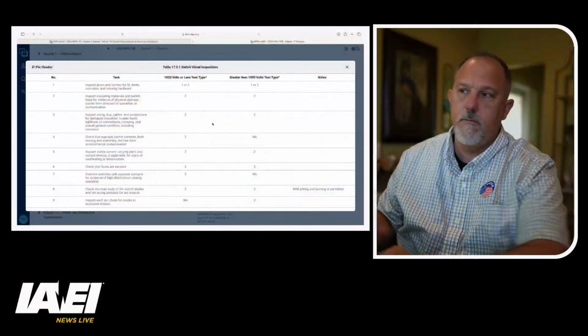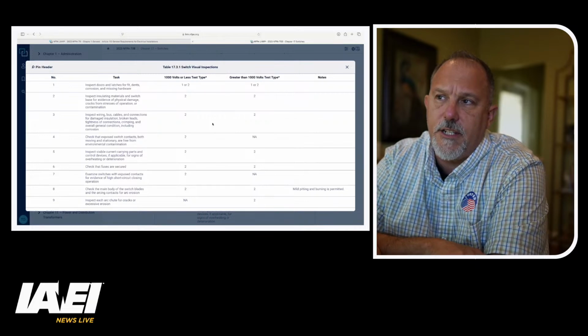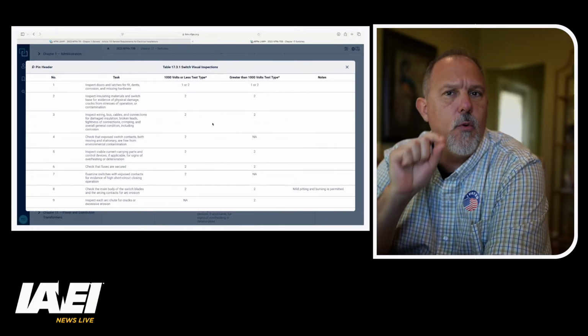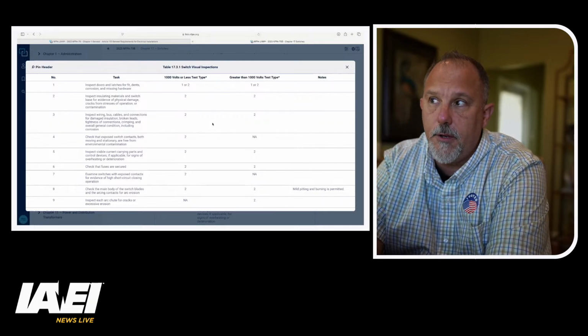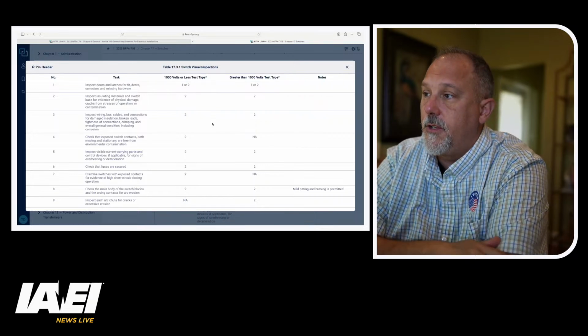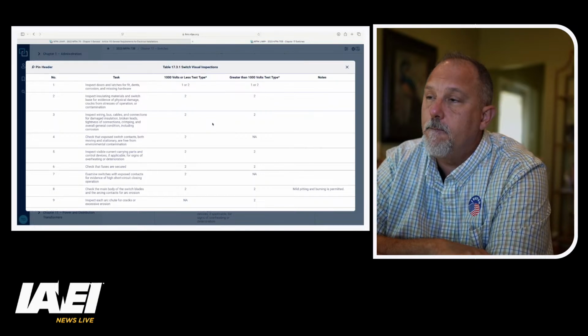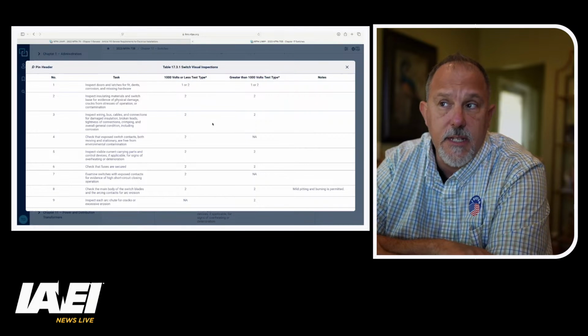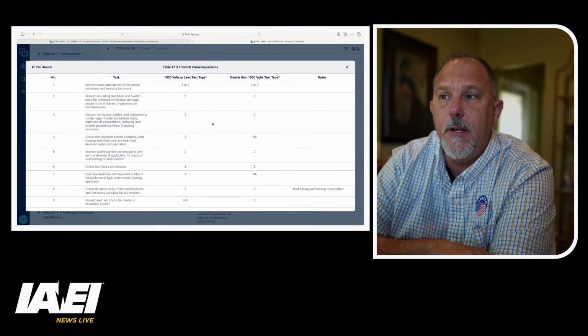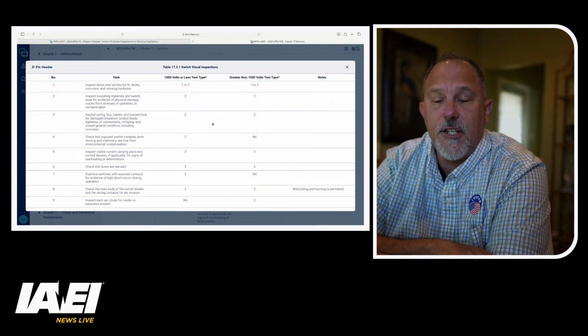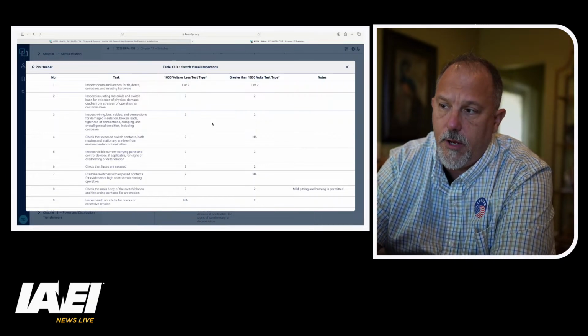So we have inspecting the doors and latches. Let's take a look. First, inspecting the doors and latches for fit. Now that's a 1 or a 2, so that can be done energized or in an electrically safe work condition. I would argue we would want to do this in an electrically safe work condition. So I do this in a 2. I don't need to energize for that. Inspecting insulating materials and switch base for physical damage. Inspecting the wiring, bus, cables, and connections. So I would establish an electrically safe work condition and then open it and look at all of these items. I don't see anything in that list that needed to be done while energized in a non-fused safety disconnect switch. How about cleaning? I would not expect any cleaning.